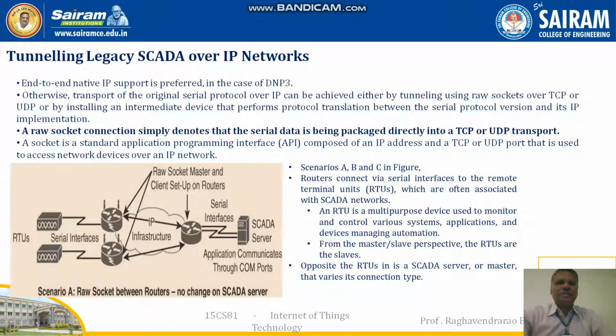You can see here in the picture how the raw socket between routers works, with no change in the SCADA server. It works directly in the TCP or UDP transport. Here a socket is a standard application programming API. It is an interface composed of an IP address and a TCP or UDP port that is going to be used to access network devices over an IP network.